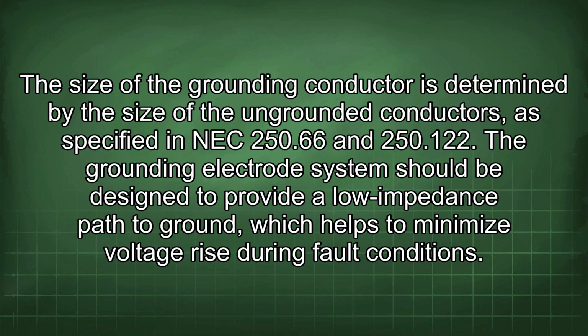The size of the grounding conductor is determined by the size of the ungrounded conductors, as specified in NEC 250.66 and 250.122. The grounding electrode system should be designed to provide a low impedance path to ground, which helps to minimize voltage rise during fault conditions.